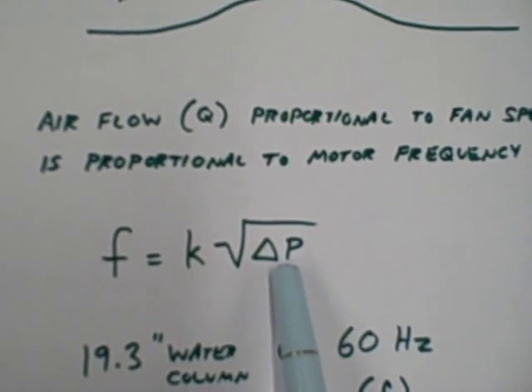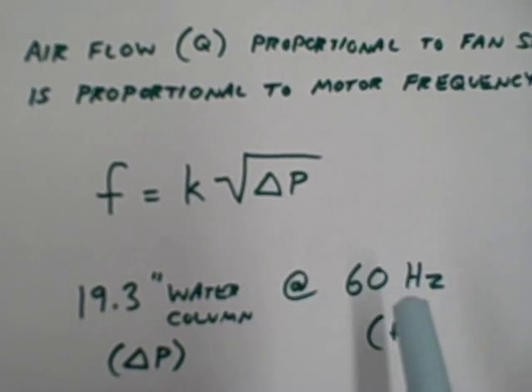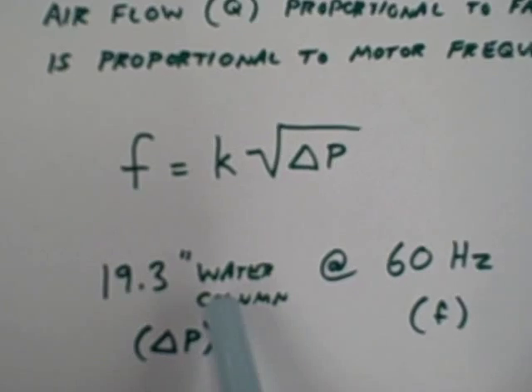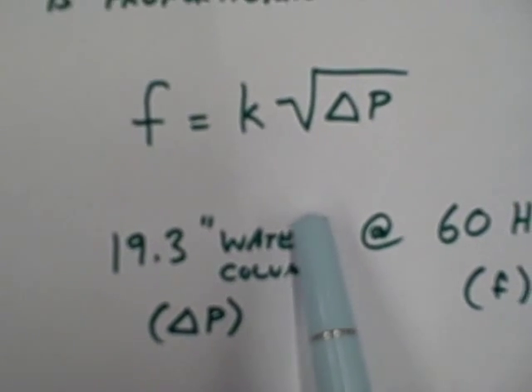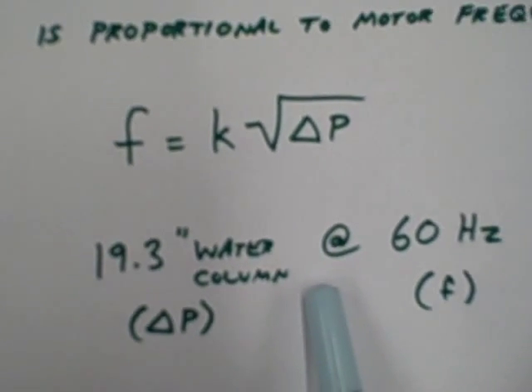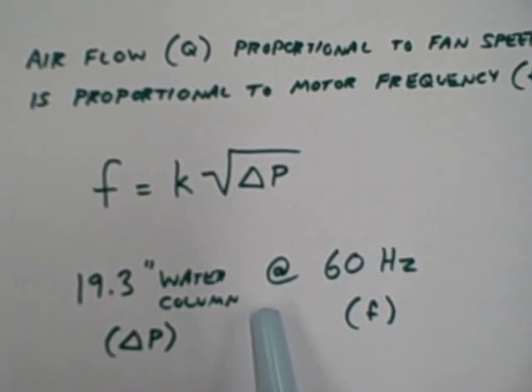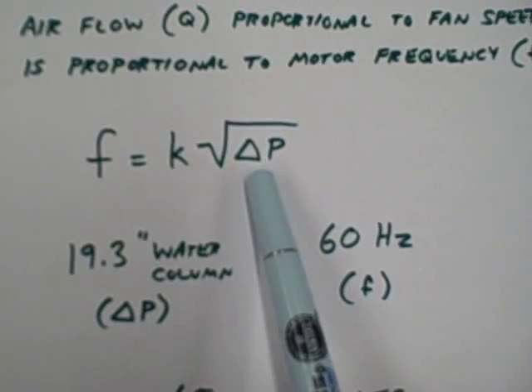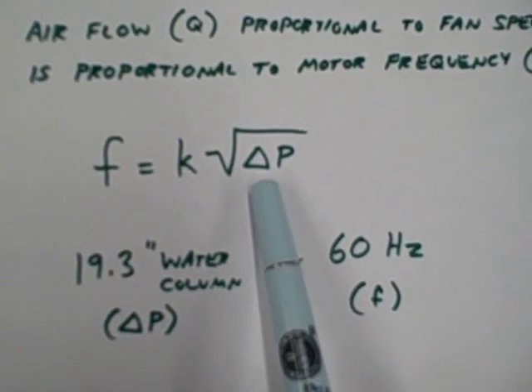In this particular case, I've done a test run, and we've found that at a motor speed of 60 hertz, a frequency of 60 hertz, we get about 19.3 inches of water column differential pressure. I'll demonstrate that here. Then what we'll do is we will change the frequency of the motor, and we'll take a look at how the differential pressure changes. You'll see right away it's not a linear relationship.